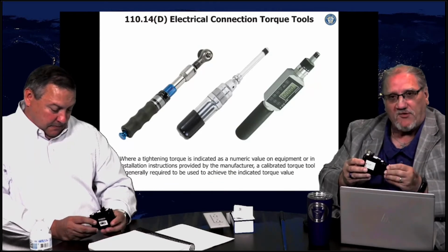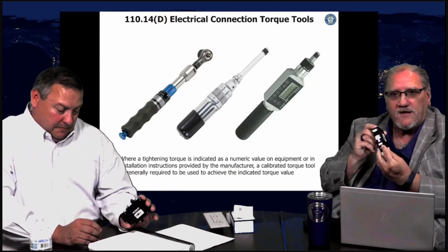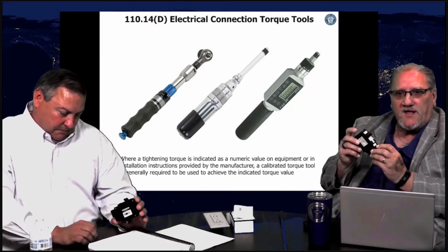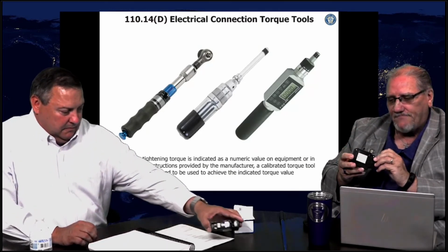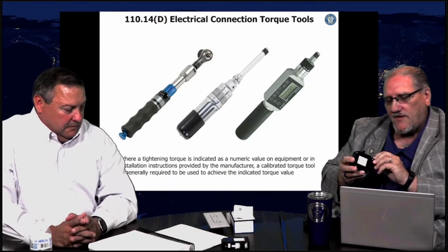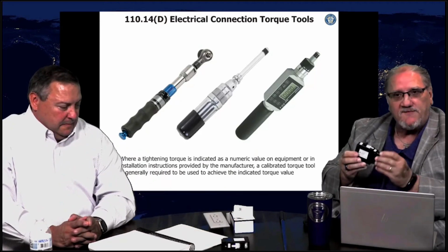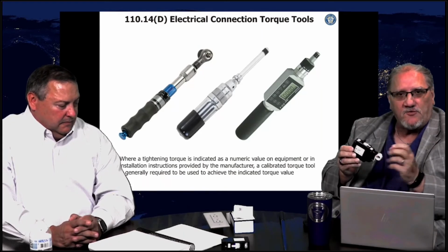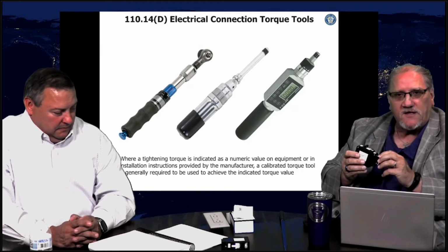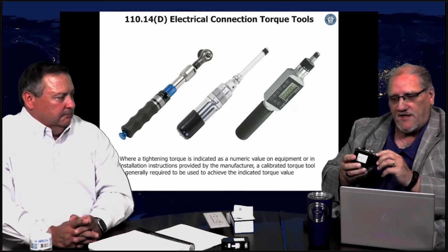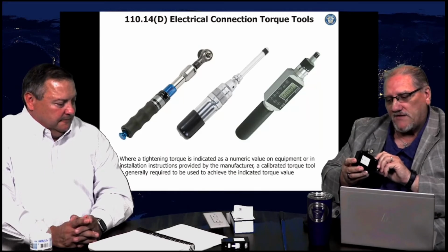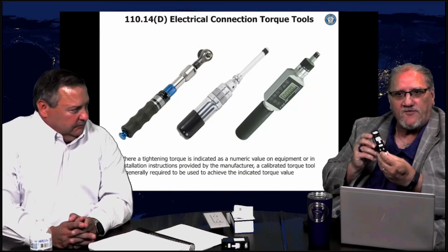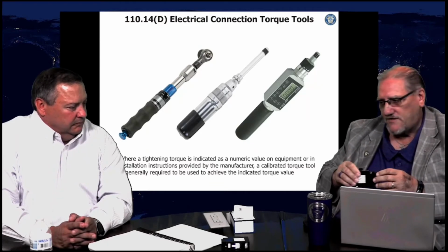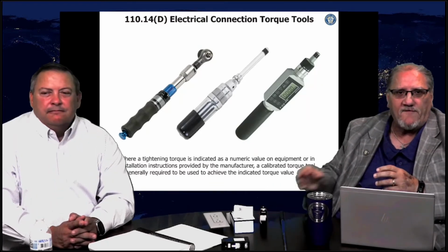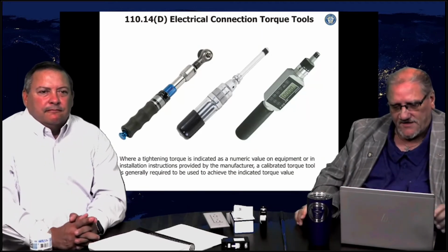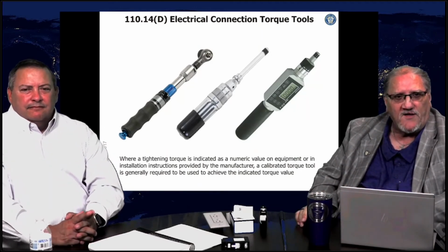Jody and I were looking at these before we started the webinar, and right there by the lugs on this particular overcurrent device, the manufacturer has put the pound-inches that needs to be achieved when you put a conductor under these lugs and tighten up this screw right here. The manufacturer gives you the 25 pound-inches, marked right on this overcurrent device. So a lot of your equipment will have those numeric values marked on it that are required.